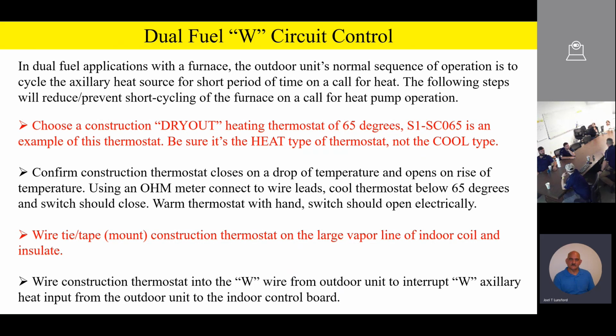We just added this about a week ago. So what we're going to do to prevent that short cycling of the furnace, if you're hooked up with a dual fuel operation, you want to make sure that if you're on a furnace, we don't want to short cycle that furnace. So we're going to choose a construction dry out thermostat of 65 degrees.